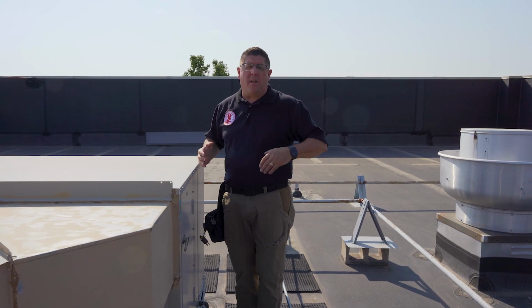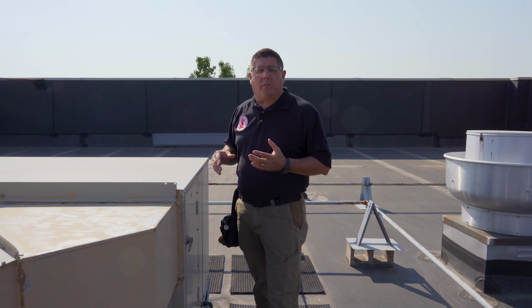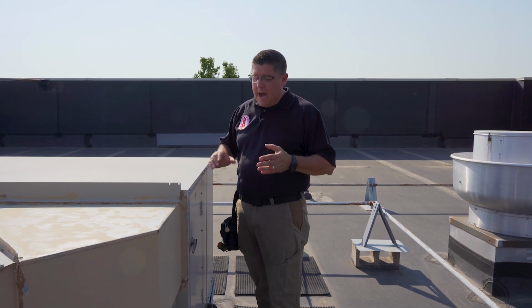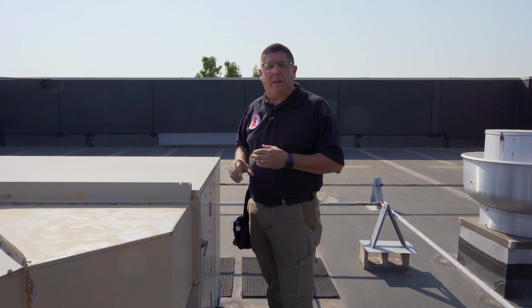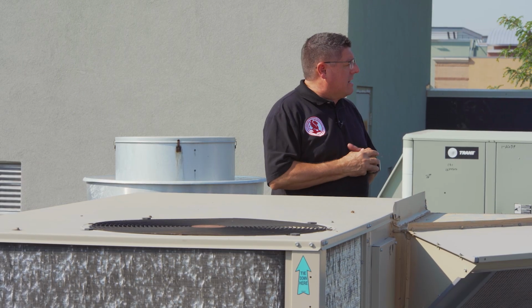We would want to encircle this unit and look for any physical damage. Let's take a look for that now. As we walk around the outside of the unit, earlier when I was talking about what I thought was the air filter chamber, it was not. The air filter chamber on this particular piece of equipment is on this side. That was the condensing chamber.